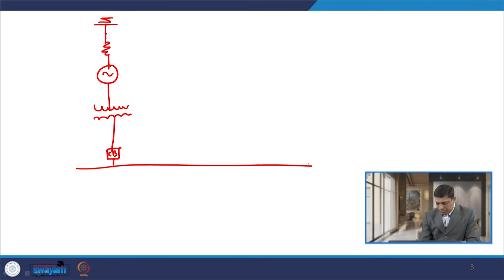So, for that let us consider a simple example. Say the generator is connected here, right, followed by, let us say, the transformer, and that transformer is connected through a circuit breaker to a bus. Say we have another generator associated with a generating transformer, which is connected to the bus through a circuit breaker. So, whenever I want to design a zone for a particular device, this generator or this transformer has its own protection zone. If I define the protection zone of the generator transformer on both sides, then further from this bus we have different lines emanating from this bus.